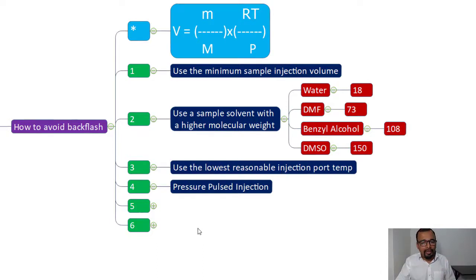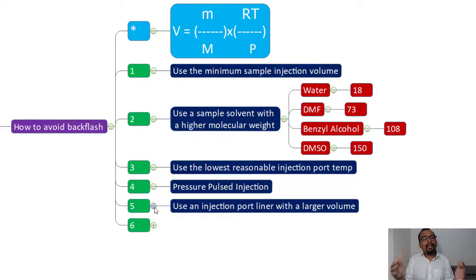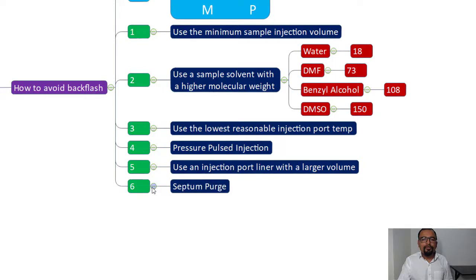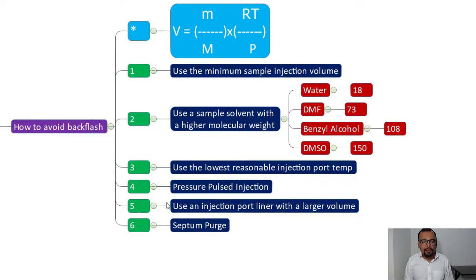The fifth solution is to use an injection port liner with a larger volume. If the glass liner volume is 0.9 mL, increasing it to 1.5 mL gives more space to accommodate the vaporized sample. The sixth solution is the septum purge — if back flash is occurring, a proper septum purge can remove vaporized sample that reaches near the septa or carrier gas line. These are the six different ways to avoid back flash.